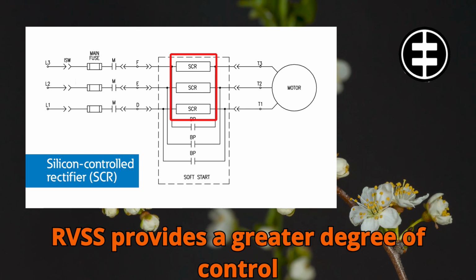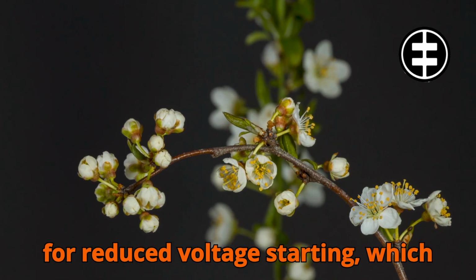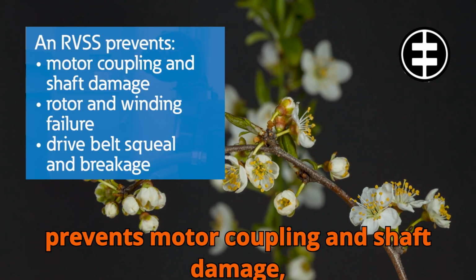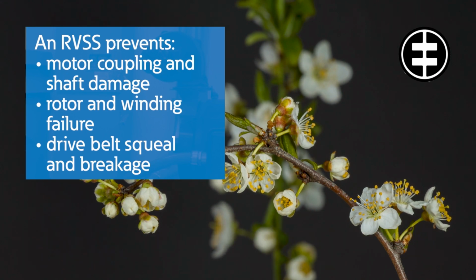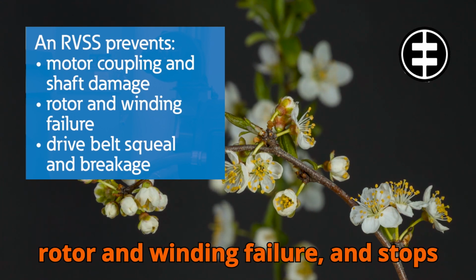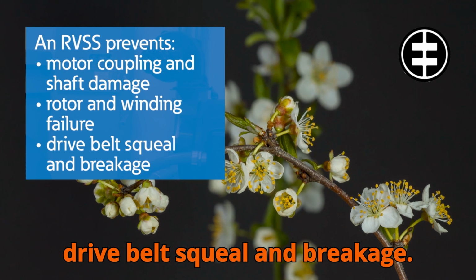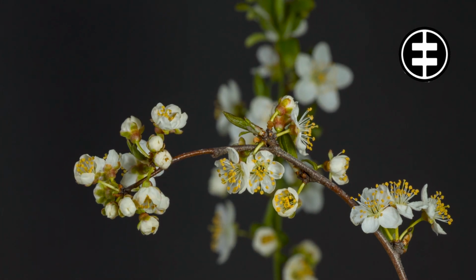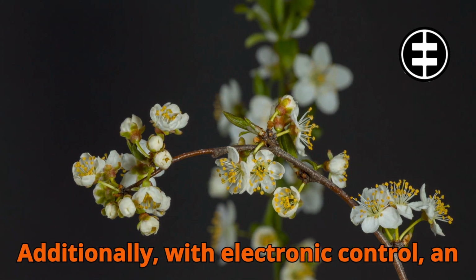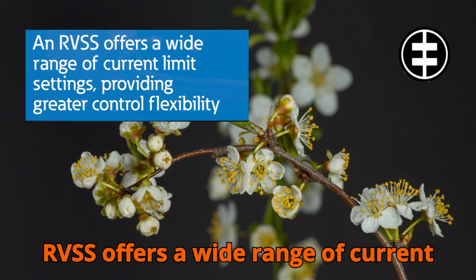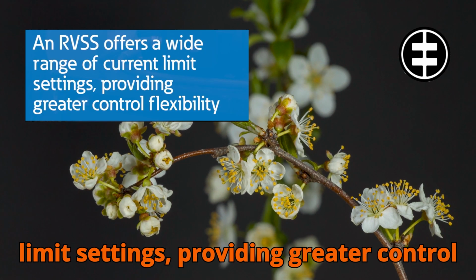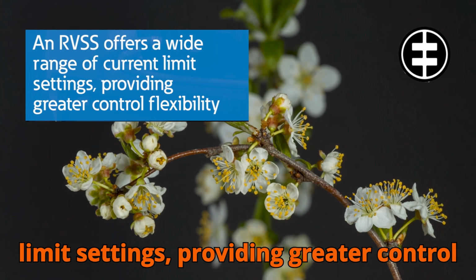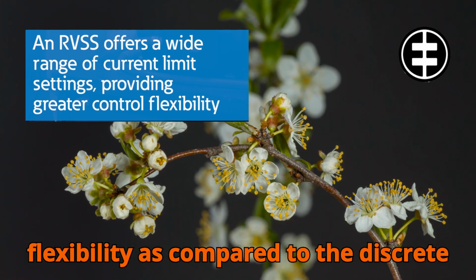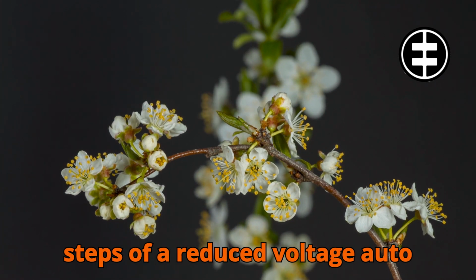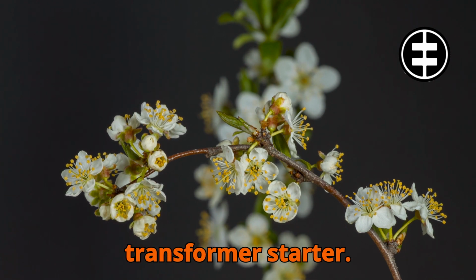RVSS provides a greater degree of control for reduced voltage starting, which prevents motor coupling and shaft damage, rotor and winding failure, and stops drive belt squeal and breakage. Additionally, with electronic control, an RVSS offers a wide range of current limit settings, providing greater control flexibility as compared to the discrete steps of a reduced voltage auto transformer starter.